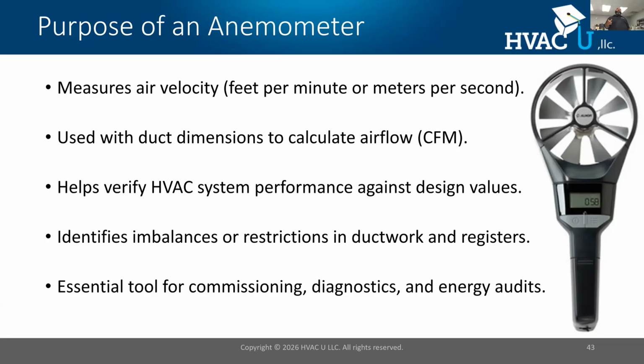When you use this, a lot of people say they're not accurate. And sometimes it comes down to the air. You're supposed to traverse the area of that register or grill, and you come up with an average. Some of the better tools actually come up with the average so you can get an average airflow. And when you do, this is a way for you to get airflow information that you might not be able to get using a flow hood at a register or grill. So is it less accurate? Yes, but it's still relatively accurate enough to help you evaluate duct systems.